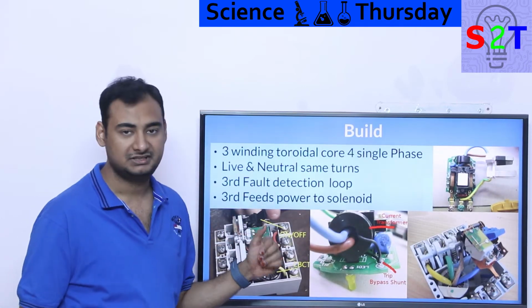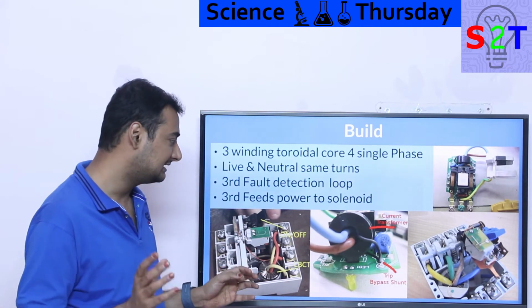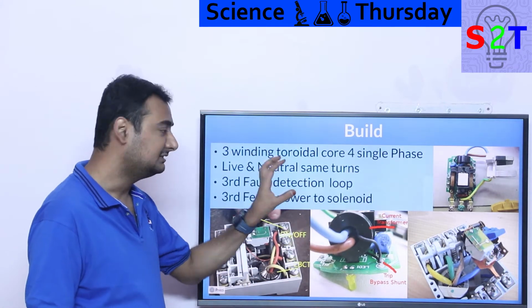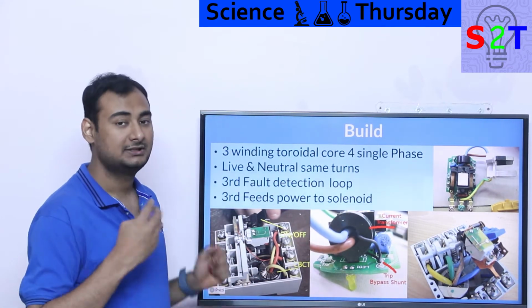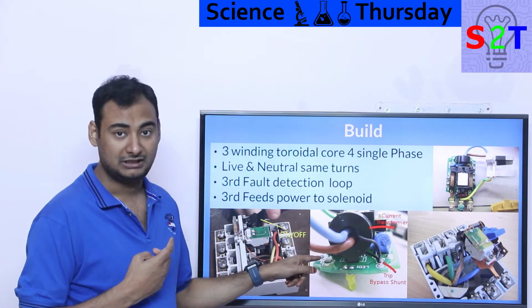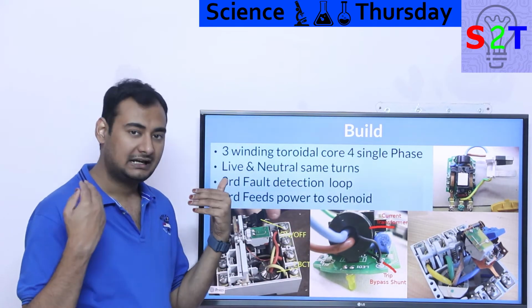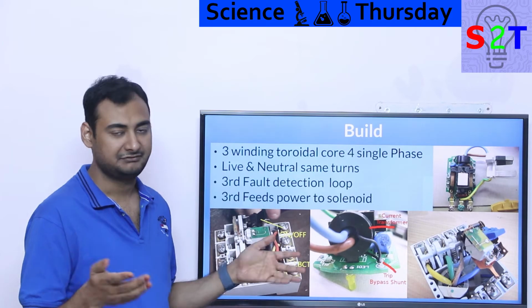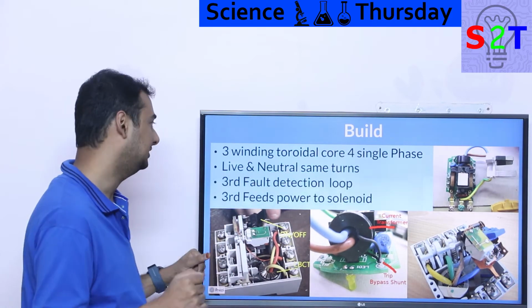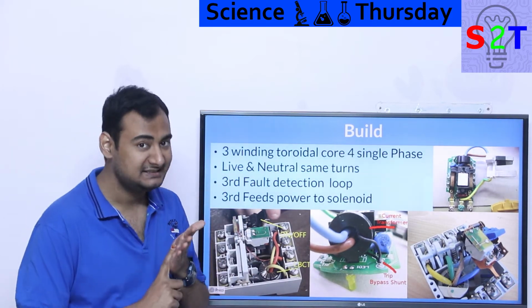Now, how is this puppy built? Generally, on a single phase system, you will simply have a toroid, and this toroid will have three coils. Coil number 1 would be live, coil number 2 would be neutral, and these two will have the same number of turns, let's say 5 turns, 5 turns, or 1 turn, 1 turn. Generally there will be 1 turn only. And the third one, that is the sensing system.